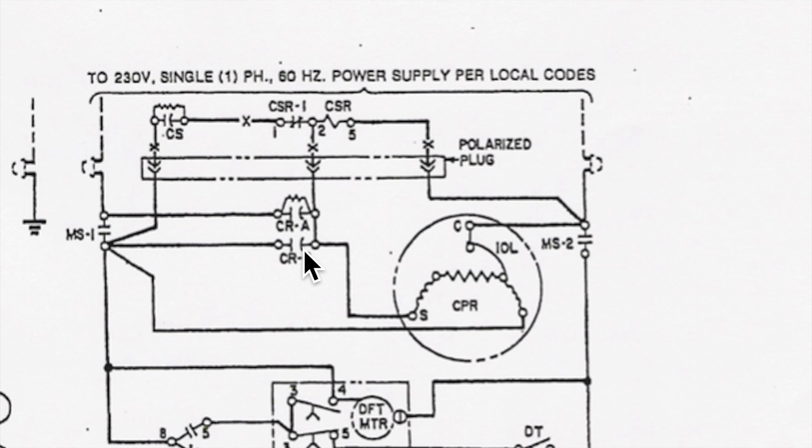But let's look at what happens then. Power comes through this capacitor, and the amperage is limited. It comes through, goes through the start winding, and the start winding is actually a load. It's not much of a load, a very low resistance. But because it is a circuit, it's going to heat up those windings a little bit, which of course is going to do what all crankcase heaters do is drive liquid refrigerant out of the compressor. So it's actually fairly simple.